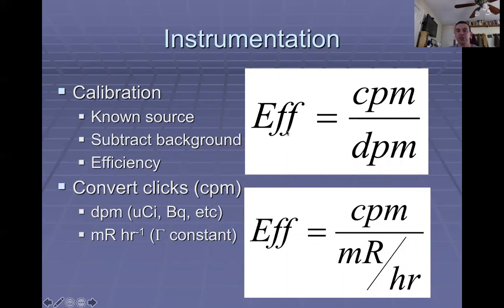So some efficiencies can be 20 to 40%. If something is 50% efficient, that means it's getting 1 out of every 2 bits of radiation that actually hit the detector. 50% efficient is asking a lot. I've talked about how measuring equipment, instrumentation, and radiation safety and health physics is very difficult. If you get something that's 10% efficient or even 1% efficient, sometimes that's a very good efficiency.